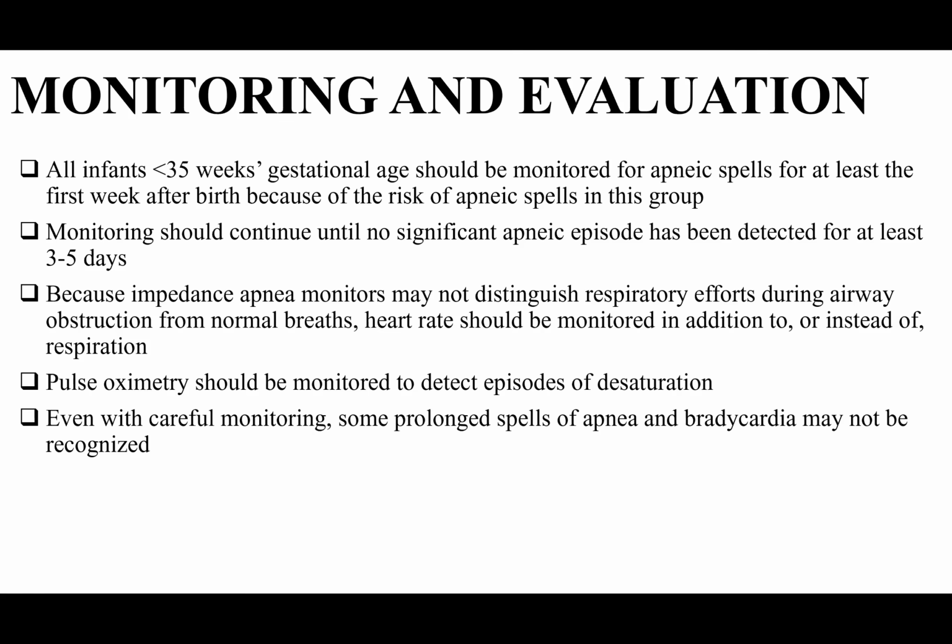When we talk about apnea and monitor, sometimes they do not catch all the apneas. The reason is because we use the impedance. We use something called RIP, respiratory inductance plethysmography. And the RIP is measuring the percentage of change of chest diameter, and therefore it might not be within the limit of the percentage of changes of chest diameter. And sometimes the monitor will not pick it up. Okay? And therefore, pulse oximetry is vital with the apnea monitor.